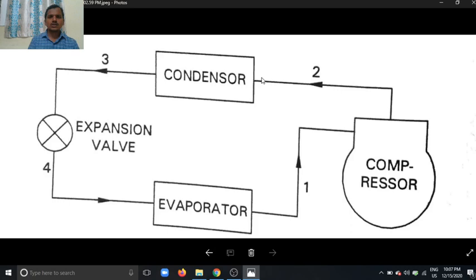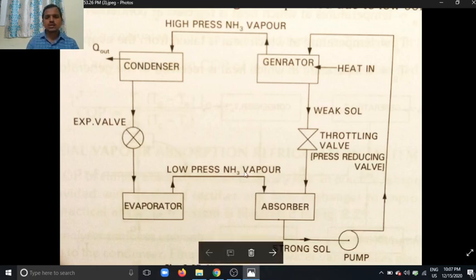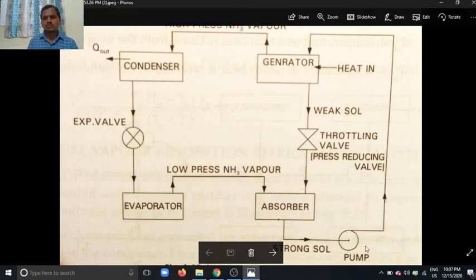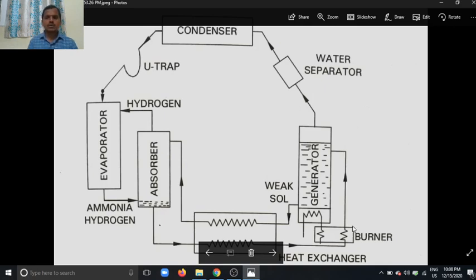In the vapor absorption refrigeration system, the sucking is done by the absorbent. The vapor ammonia is absorbed by the absorbent, which is water, and this water is converted into a strong solution. The strong solution is then pumped to the generator by a pump — that sucking is generated by the absorbent and the strong solution is pumped to the generator with the help of the pump.